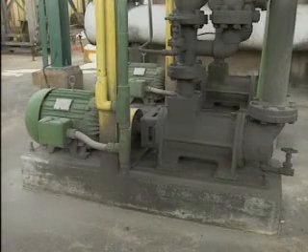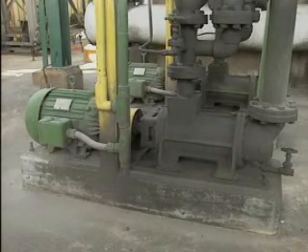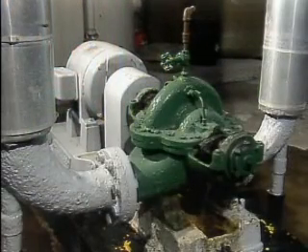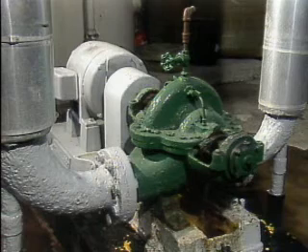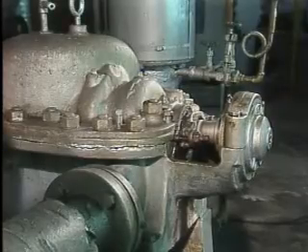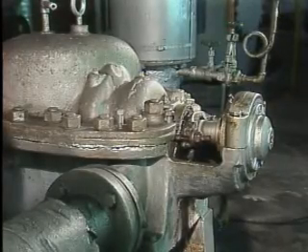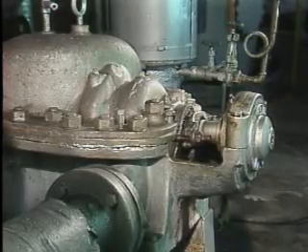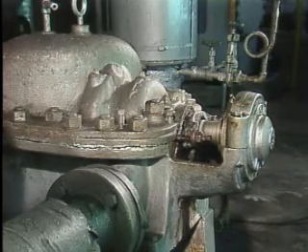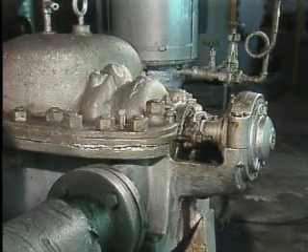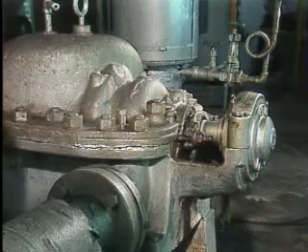Many types of equipment have a rotating shaft that penetrates a stationary housing. In cases where the equipment moves a fluid, some material or device is needed to seal around the shaft to keep fluids from leaking out and contaminants from getting in. Sometimes packing material is used to seal around the shaft, but most equipment that uses packing requires a small amount of leak-off to reduce friction between the packing and the shaft.